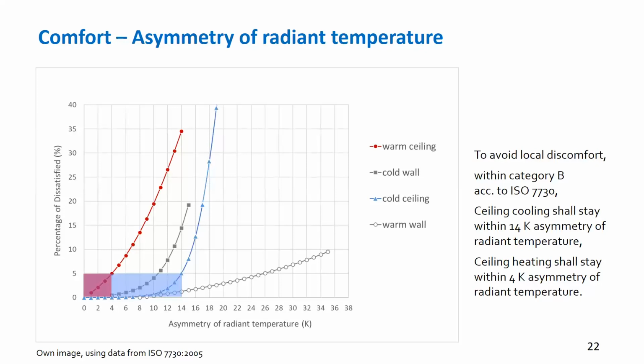I redraw the famous local discomfort chart of ISO 7730, giving the percentage of dissatisfied which have to be expected from asymmetry of radiant temperatures for four different kinds of radiative cooling and heating solutions. In red, it's the warm ceiling. In blue, it's the cold ceiling. And in gray, it's the cold wall. And in gray, it's the warm wall. To be read like this, if you go for a warm ceiling and enter a radiant temperature asymmetry higher than 4, you have to expect or be aware of a percentage of dissatisfaction of 5% of the people. And strict ISO says design for this 5%, then you're in category B of the ISO 7730 standard.